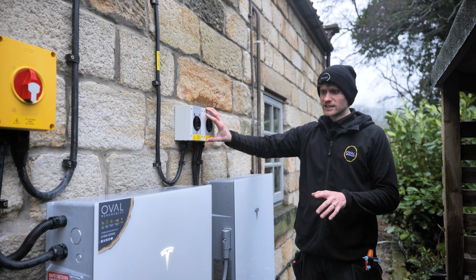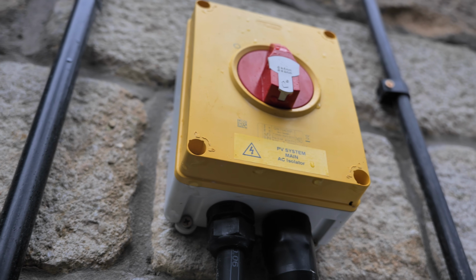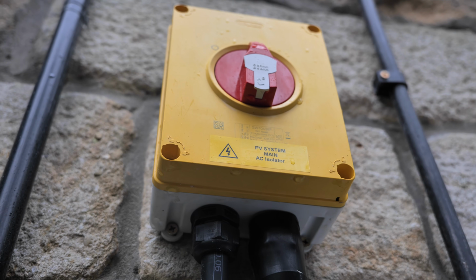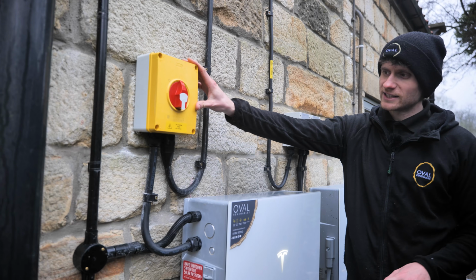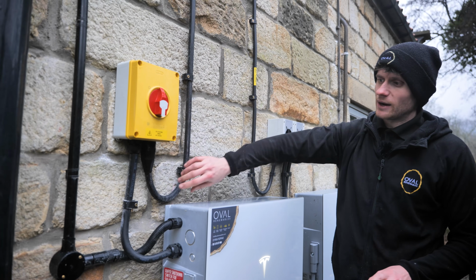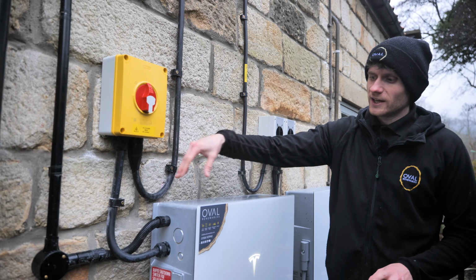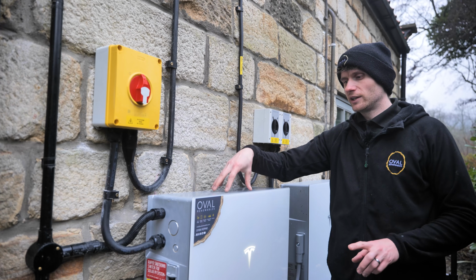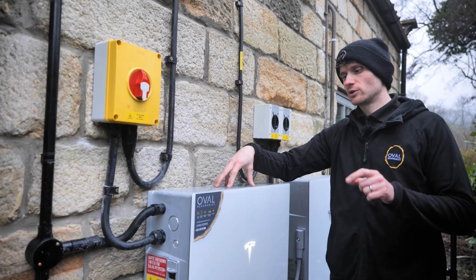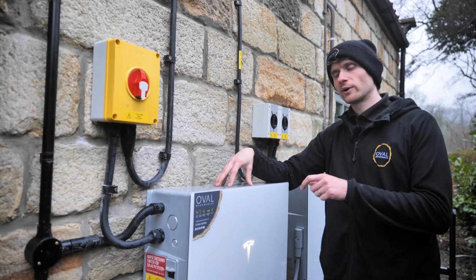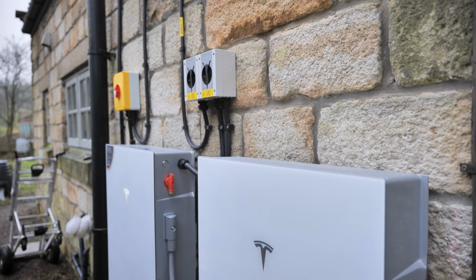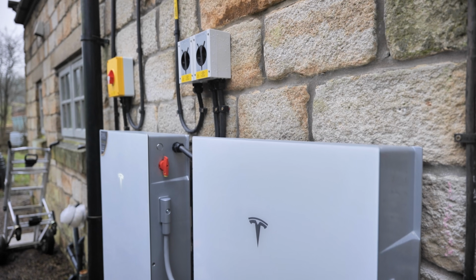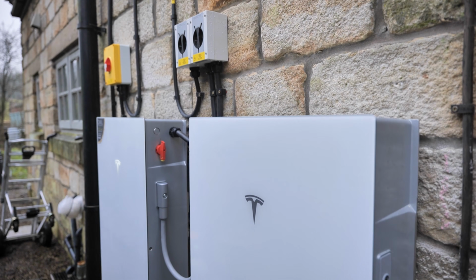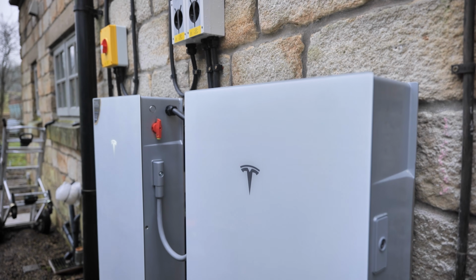That's our DC isolation. We've then got our AC isolation, which is this big 63 amp rotary AC isolator, fed by our 16mm 3-core armoured cable. This system has full DNO approval to allow this Tesla Powerwall 3 to discharge at 11.04 kilowatts, so we needed to be able to switch that full load, which is why we've got that size isolator.